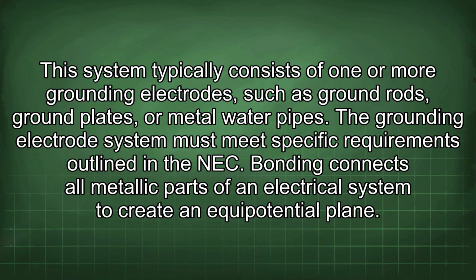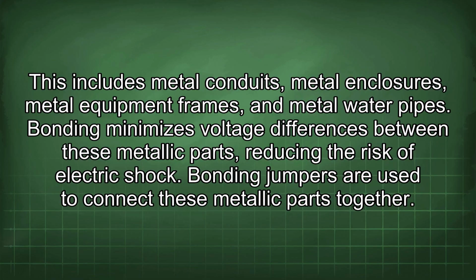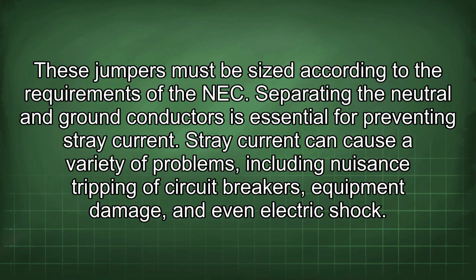Bonding connects all metallic parts of an electrical system to create an equipotential plane. This includes metal conduits, metal enclosures, metal equipment frames, and metal water pipes. Bonding minimizes voltage differences between these metallic parts, reducing the risk of electric shock. Bonding jumpers are used to connect these metallic parts together. These jumpers must be sized according to the requirements of the NEC.